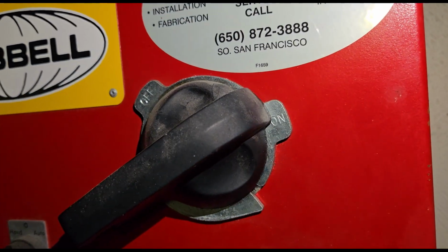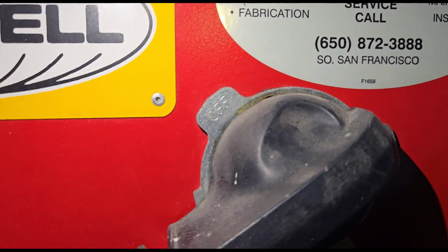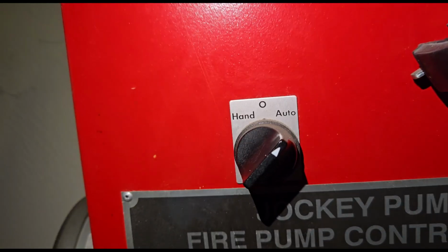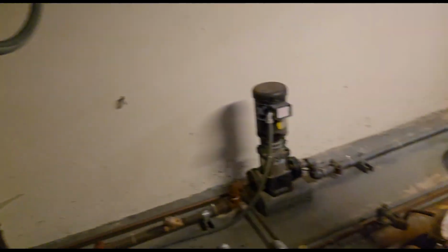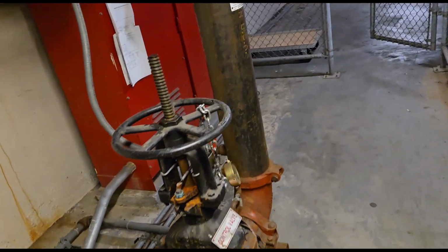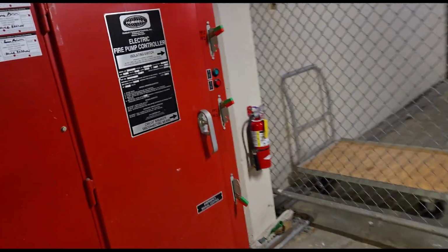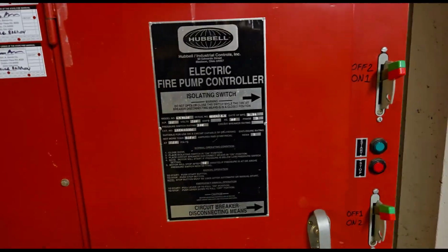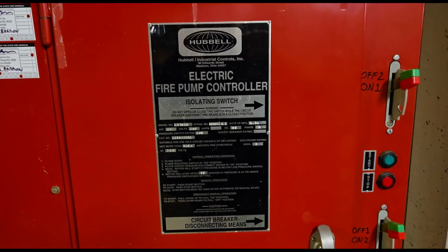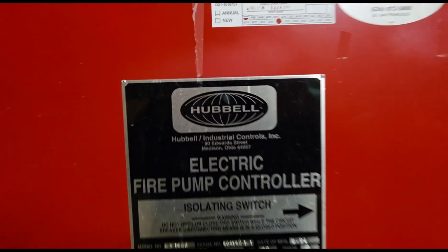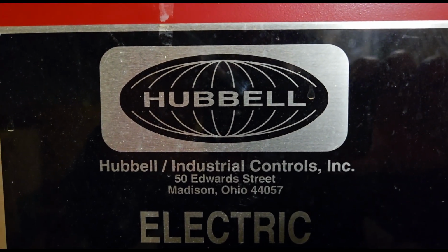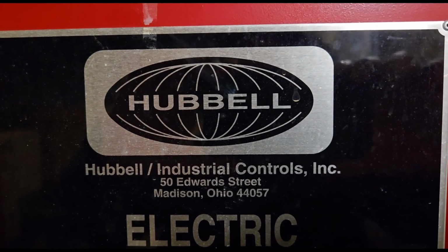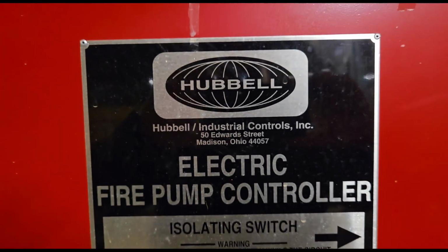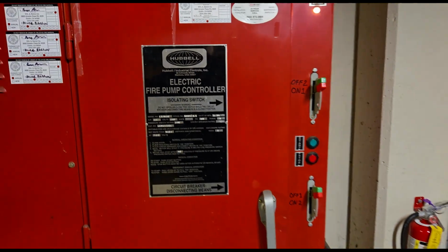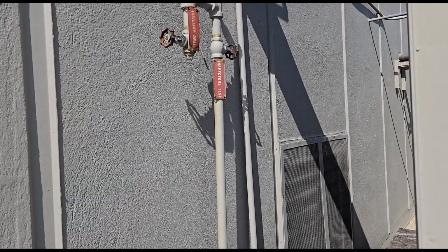So it's on the on position, and it's set to auto. We don't even touch the jockey pump controller. Everything, we're just turning off and on the pump. So that is how you bypass the Hubbell Industrial Controls Inc. electric fire pump controller.